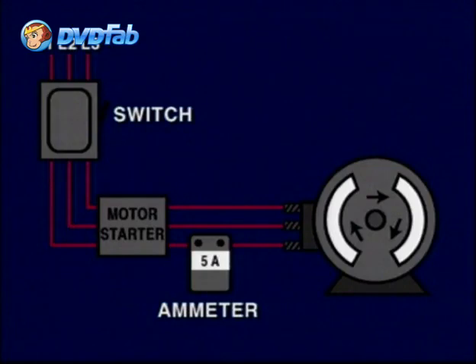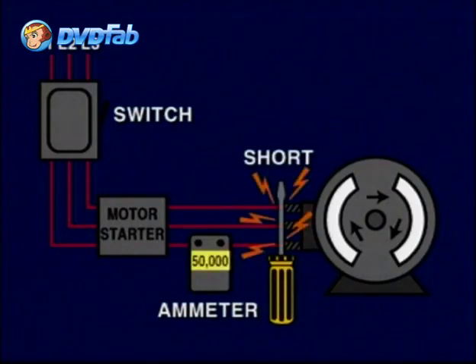Whereas overload currents are normally in the 1 to 6, or, as in motors, 6 to 10 times the normal current, short-circuit currents are quite high. These single-element fuses may be subjected to a short-circuit current of 50,000 amps or higher. The response to these currents must be extremely fast to avoid serious damage and run the risk of fire. In fact, the response of a fuse must be within a matter of a few milliseconds in the event of a large ground fault.